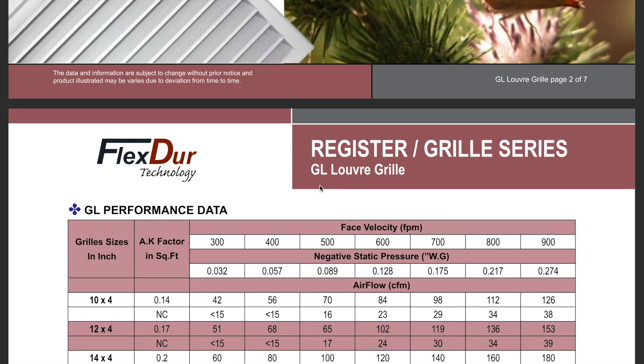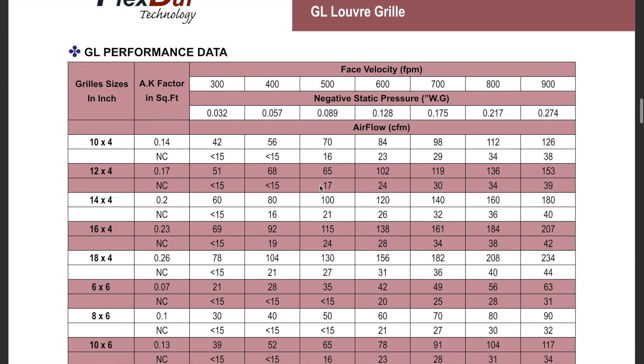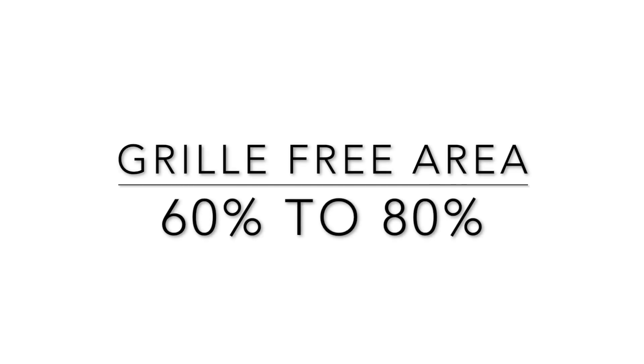This is a general method to size return air grill because most of the time you won't know the free area of the grill. For HVAC engineers, manufacturers are required to provide their grill specifications, meaning we know the free area of their grill. Usually, we select return air grills from the chart provided by the manufacturer — we don't need to calculate the grill size because the airflow capacity of each grill size is stated in the chart. Most of the time, we see grills constructed with 60 to 80% free area, and the average free area is 70%.